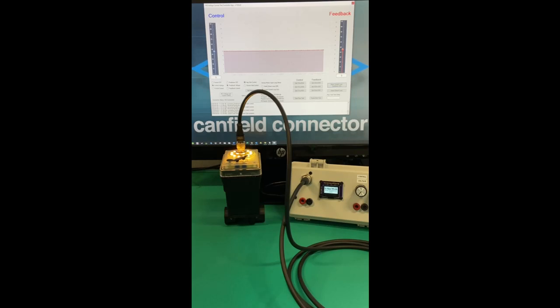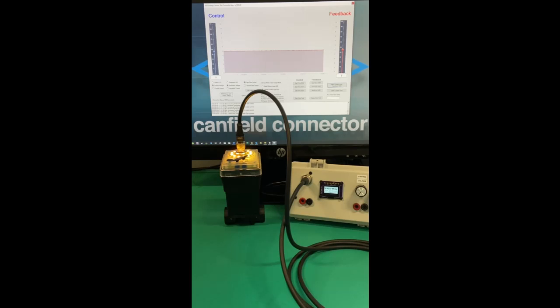As we saw, the feedback signal then rose back up from a value of 4 volts to match the control voltage value of 5 volts, at which point the inputs were within hysteresis and the stepper valve stopped moving.